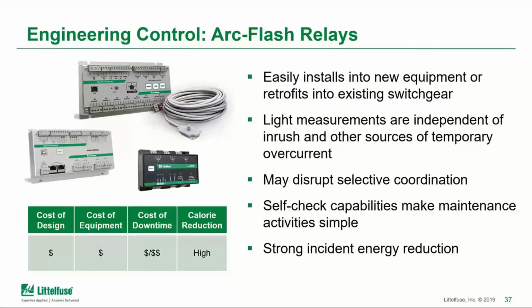So these relays use light as their detection, the main detection driver within the equipment. And if light is detected, then a trip signal would be sent to a shunt trip breaker, or if it's paired with a quenching device. But the detection with the light can happen very, very quickly, and industry standard values are less than 1 millisecond, which is almost instantaneous.